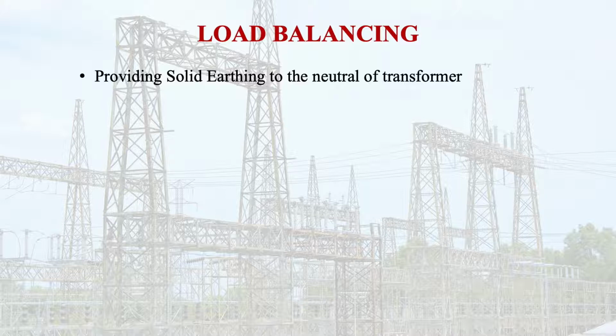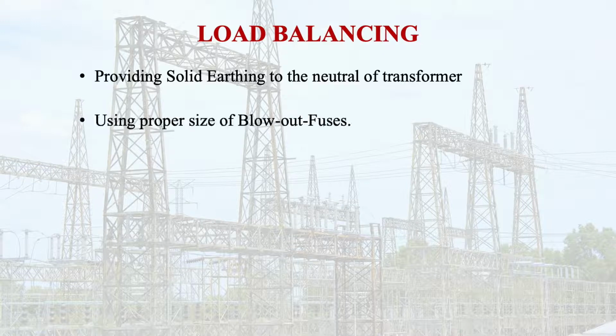But due consideration must be given to providing solid earthing. In the case of the transformer, it is also essential that solid earthing to the neutral of the transformer is provided, along with proper size of blowout fuses. If there is some unbalance, some phase may carry more current than its current carrying capacity, so the blowout fuse should be there.